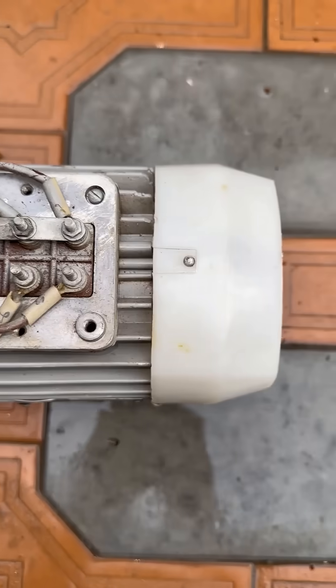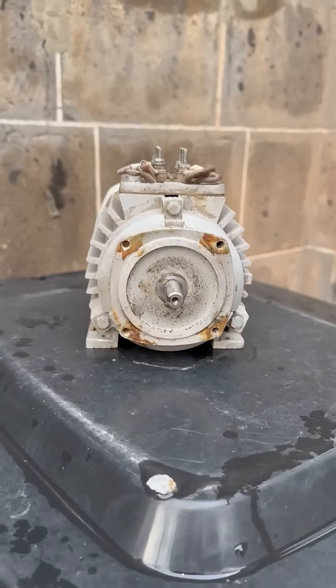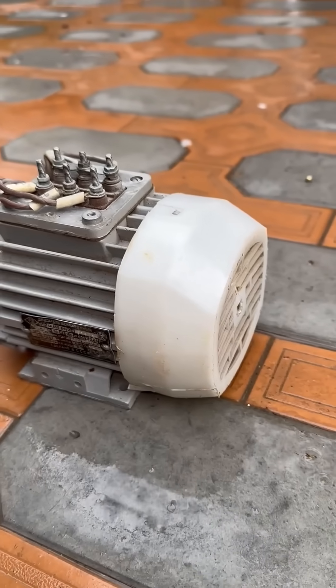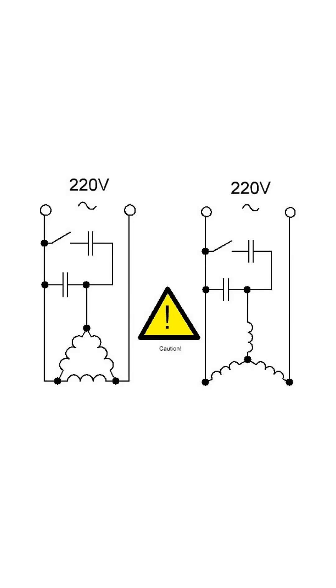And in cases where the motor starts under load, meaning the initial starting currents are significantly higher than the rated value, a starting capacitor is also required.